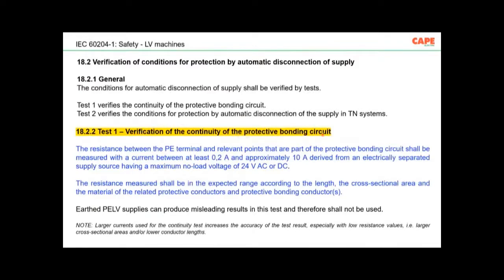Verification of continuity of the protective bonding circuit. The resistance between PE terminals. So where do you have the PE terminal? The PE terminal is in the machine. The resistance between the PE terminal and the relevant points that are part of protective bonding circuit shall be measured with a current between at least 0.2 ampere and approximately 10 ampere derived from an electrically separated supply source. So basically what it says is, after making the connection, you are supposed to test the resistance of that particular connection with a meter, electrically isolated supply, having a test current of maybe about 10 ampere. I would recommend that if you go for an Indian meter, then you should have a test current of minimum 10 ampere. Otherwise, you will not get the correct value.